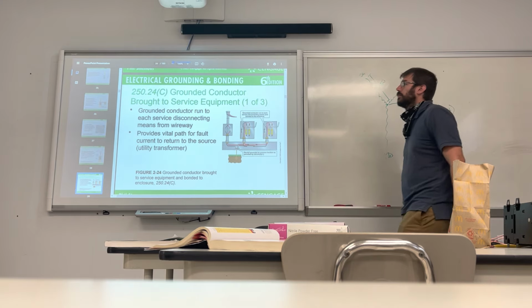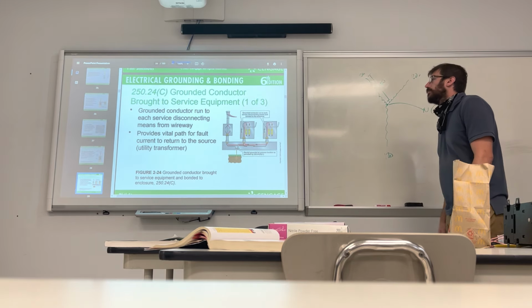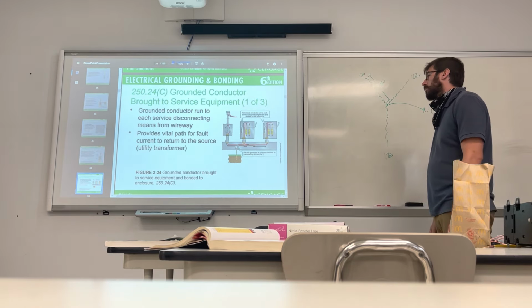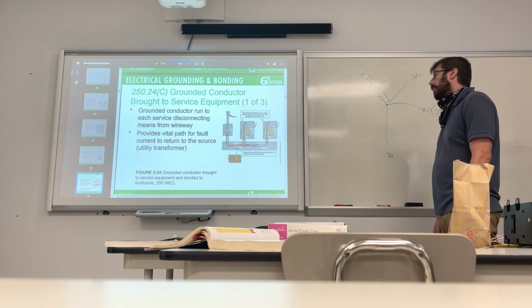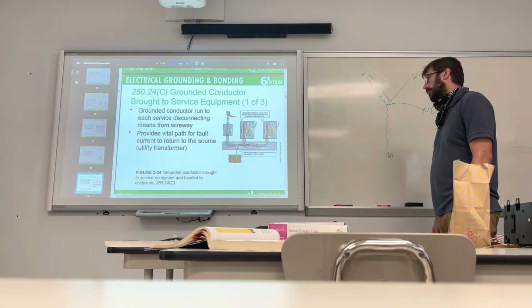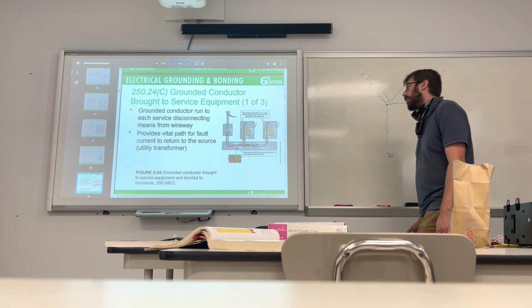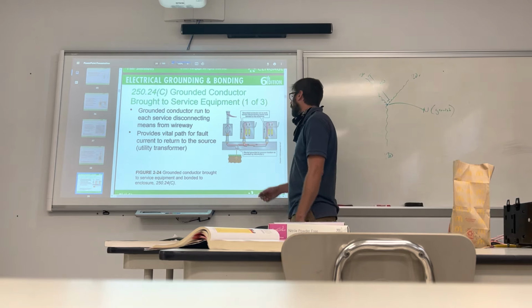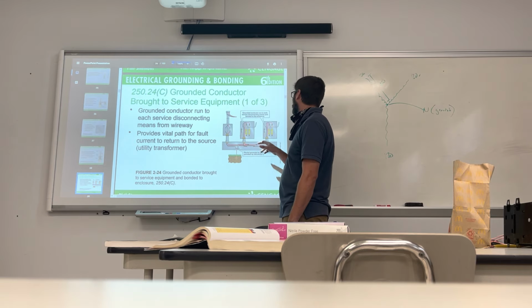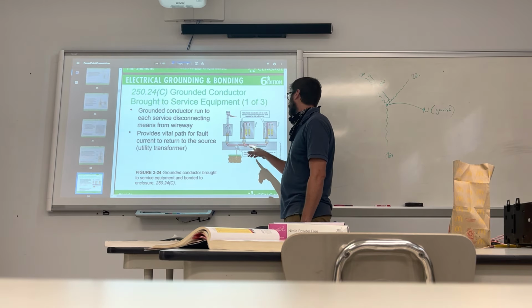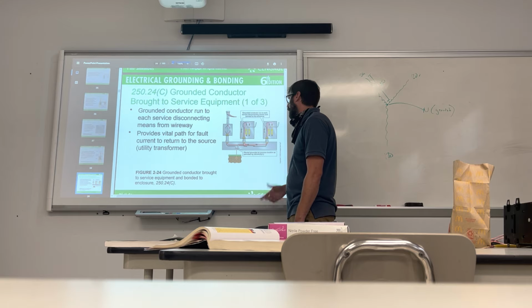Take this one too. Grounded conductor brought to service equipment. Grounded conductor run to each service disconnecting means from the service line. Provides a vital path for fault current to return to the source. You can see here, it's all everything that I mentioned before. It's grounded to the box, grounded to the box. It's going through that. It's going through the ground. Taken care of.